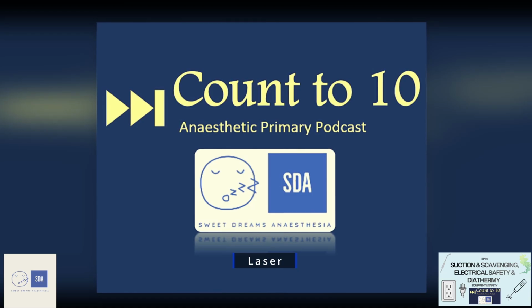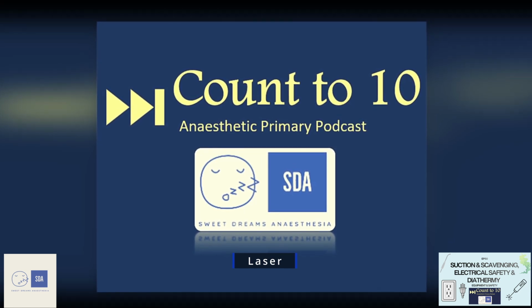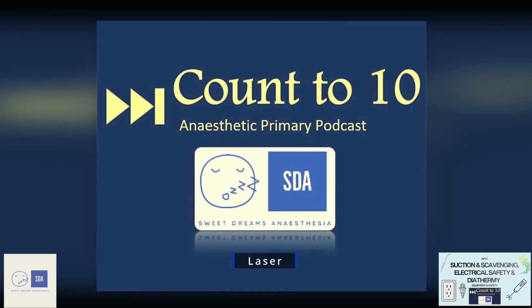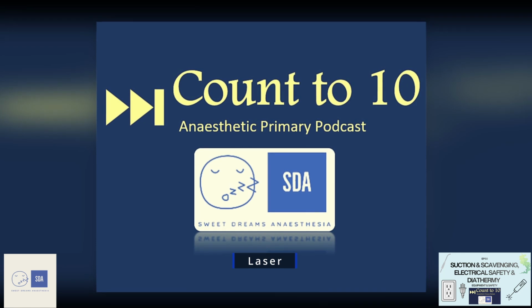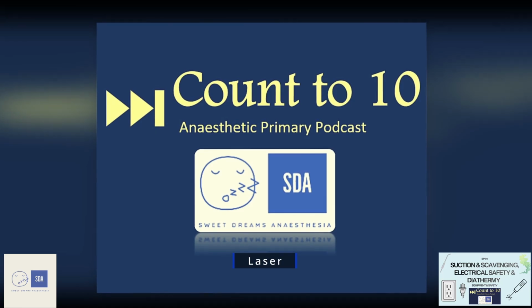Importantly, when it comes to laser fires or electrical fires, you need the same three components to ignite a fire. A fire is a chemical reaction that liberates energy in the form of heat and light. There are three requirements for any fire. One, a combustible substance. For the patient, this could be the endotracheal tube or the drapes. The second component is an oxidizing agent, a substance that can support combustion, typically oxygen or even nitrous oxide. And thirdly, an ignition source. This could be a laser or a diathermy, something with high enough energy to cause an oxidative reaction.